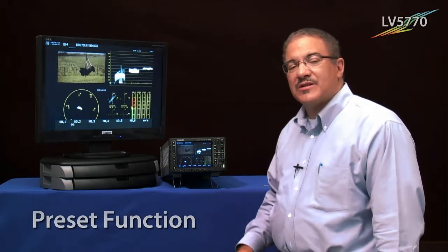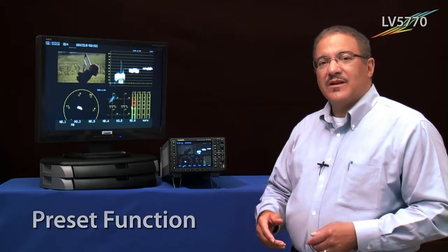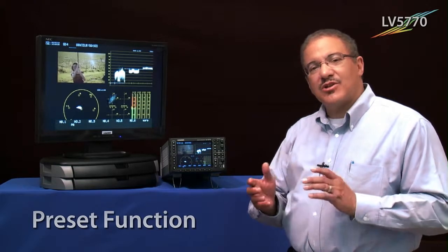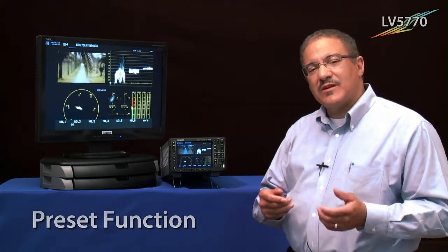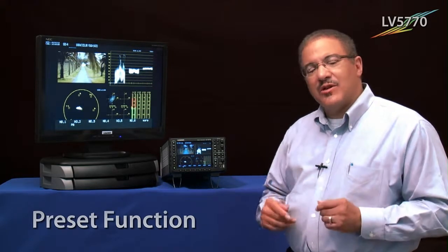And that's how simple it is to actually save a preset. Presets, again, can be very, very handy to be able to recall a particular configuration, especially if somebody makes a lot of changes or you've got people who like to have their own specific configuration. Saving as a preset makes it very easy for them to recall it no matter how the unit may be changed.